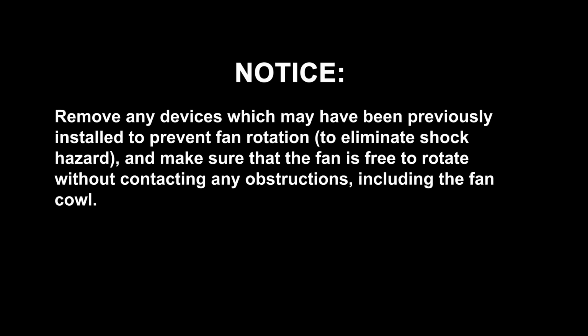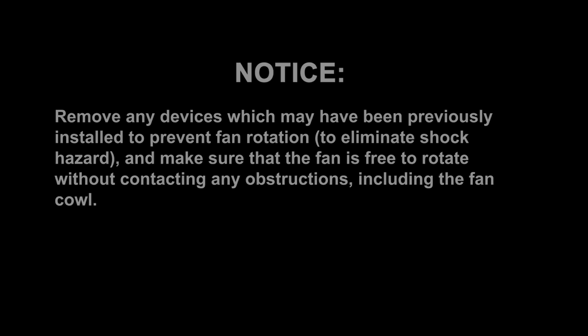Before testing, verify that the fan system is clear of all personnel and tools so that motor rotation will not cause injury or equipment damage. During testing, have someone stand by outside the tower to make sure nobody enters the tower during this process. Remove any devices which may have been previously installed to prevent fan rotation to eliminate shock hazard, and make sure that the fan is free to rotate without contacting any obstructions, including the fan cowl.